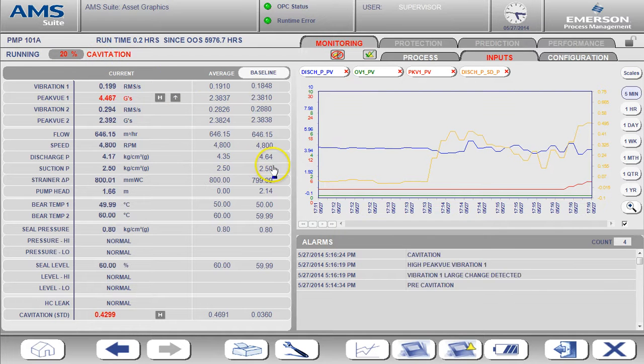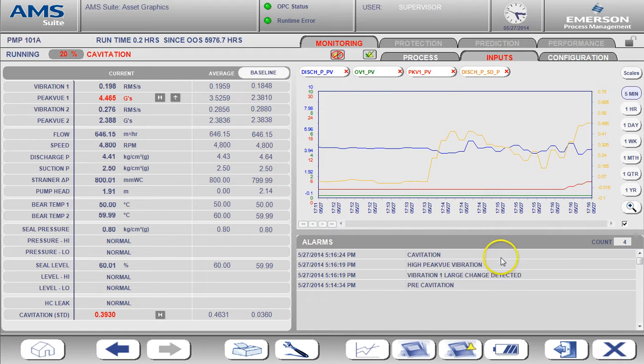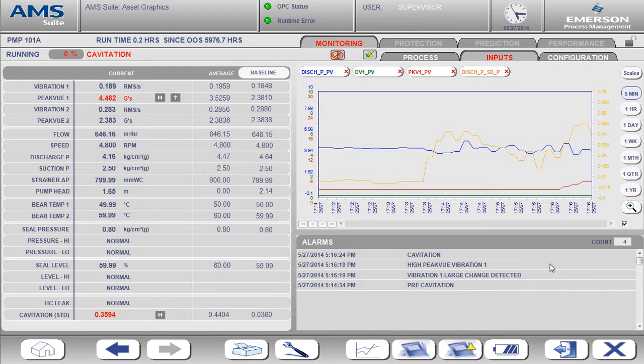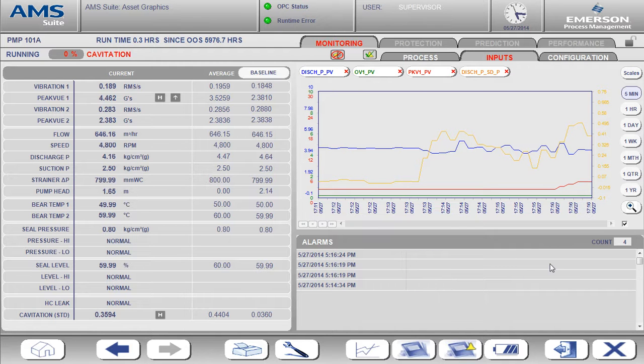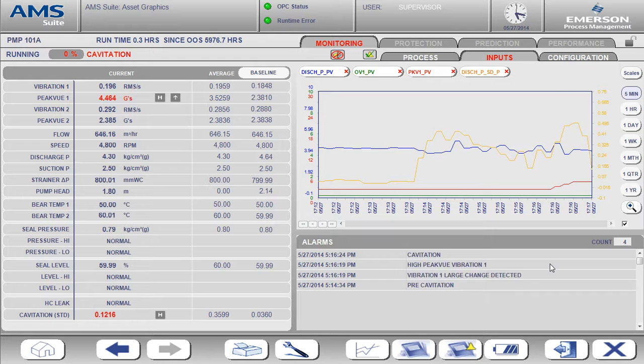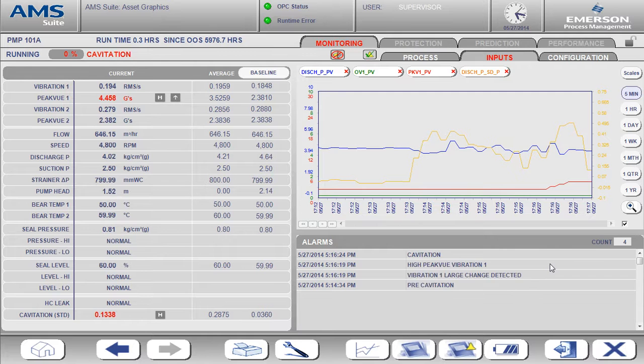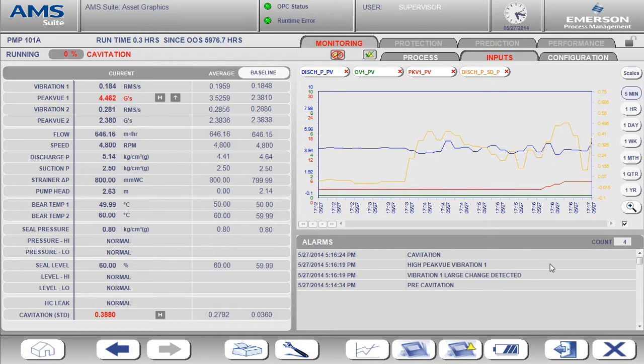This is a great example of how we are using both process and asset data to determine overall asset health. In this case, it was the process measurement of discharge pressure that detected the pre-cavitation condition alone. Then, the combination of high PeakVue and standard deviation of discharge pressure triggered the critical cavitation alert.